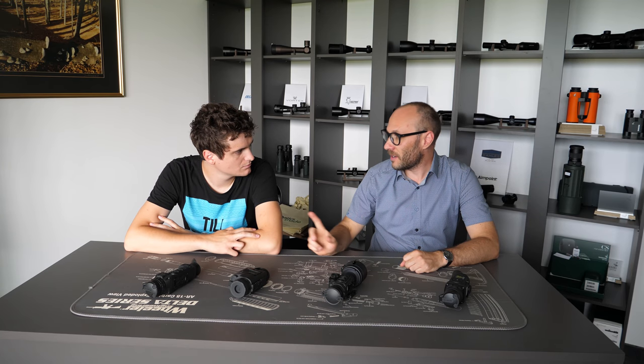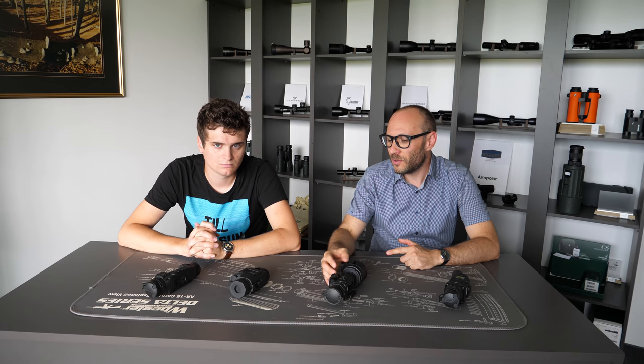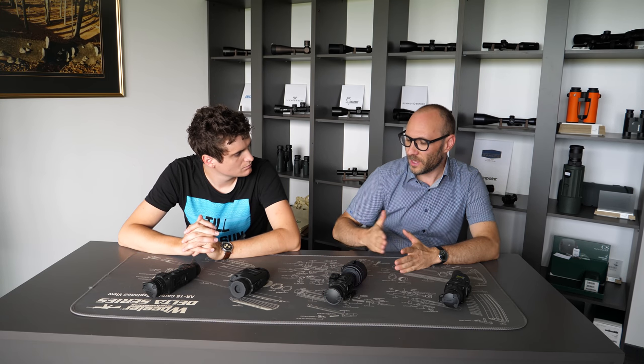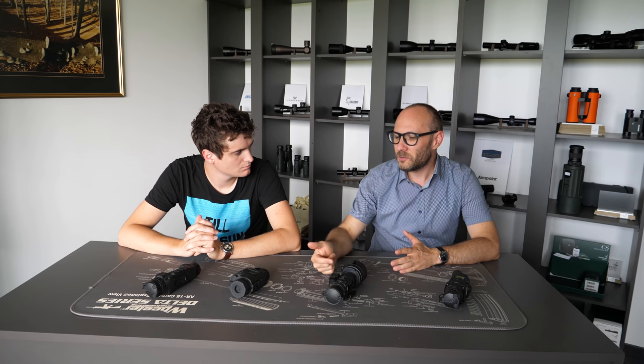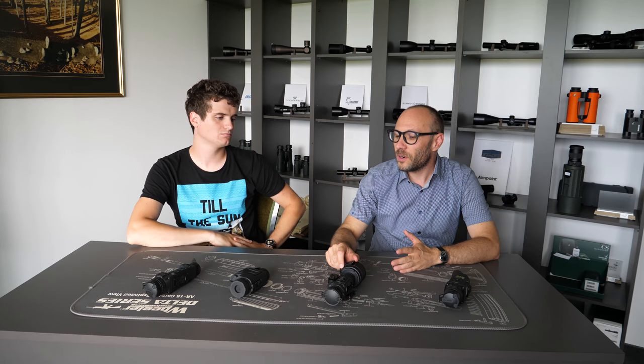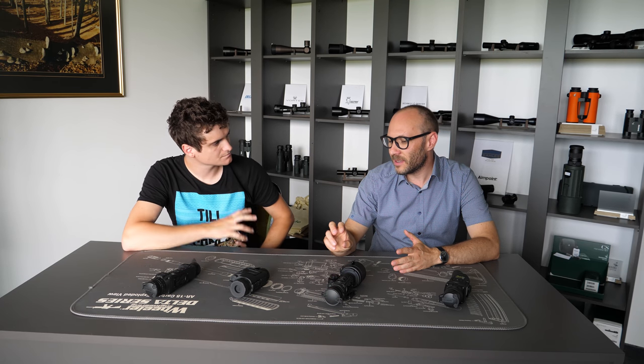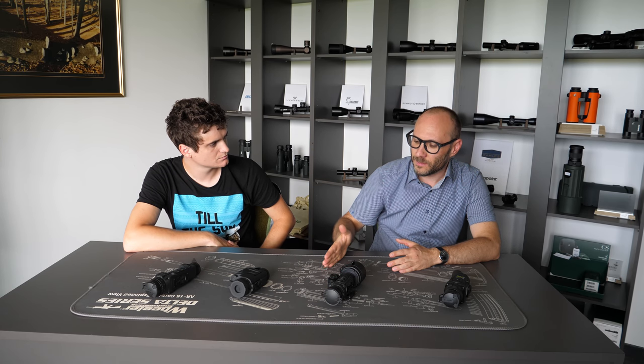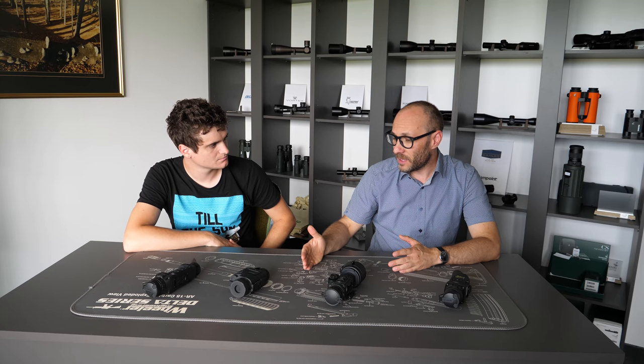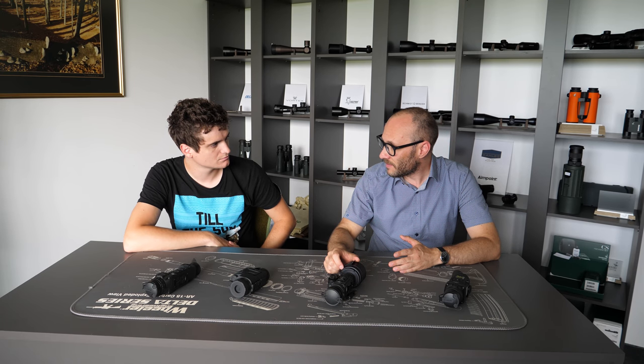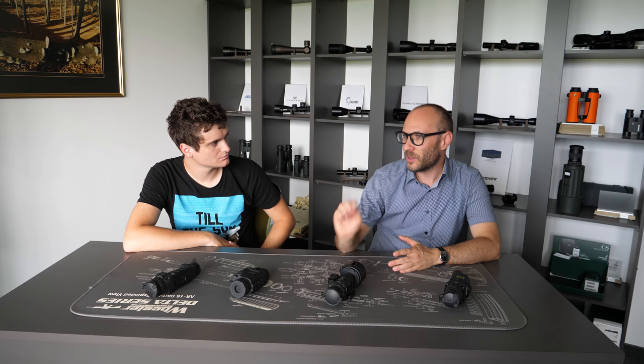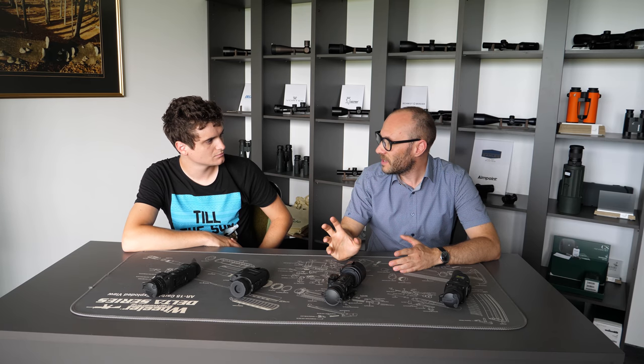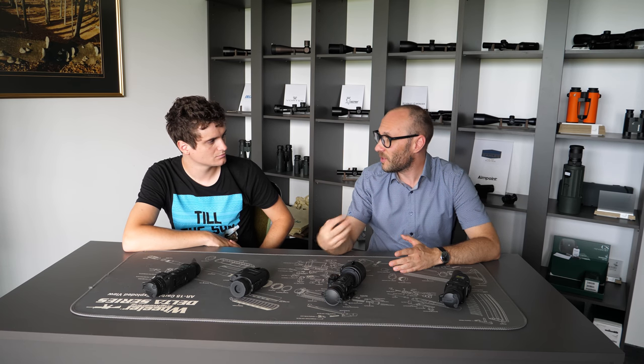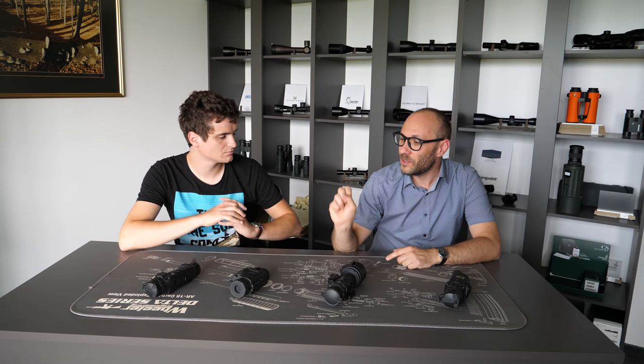Now, the modes of calibration are what we are explaining here. There are basically three different modes. One is that the calibration process is automatic. That means there is a software algorithm inside which either has a timer, every 1 minute or every 30 seconds, and runs the recalibration of the sensor, or there is software which sees how the image quality fades, and at one stage when the image quality is not good enough anymore, it runs the calibration. You notice this immediately because your image freezes for a second or two, because at the time when the sensor is recalibrated, you're not getting any image. So this is the first thing you notice, that the image freezes.